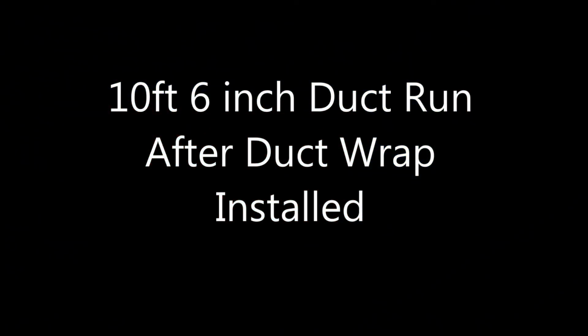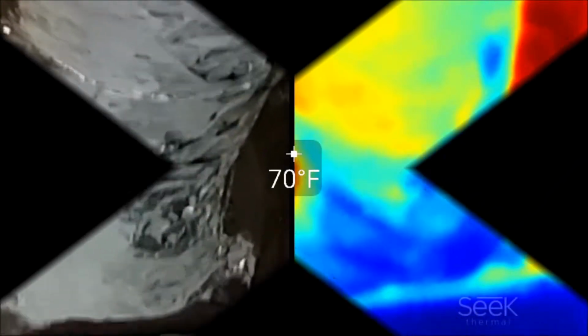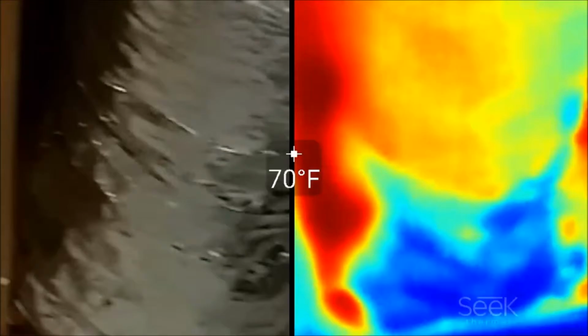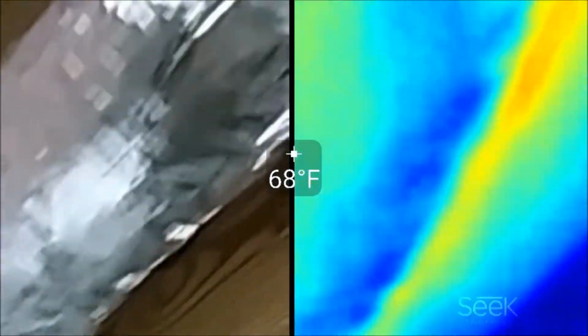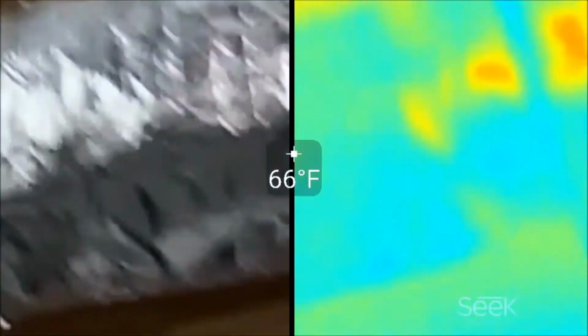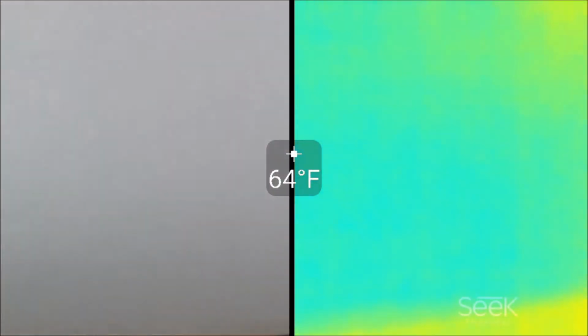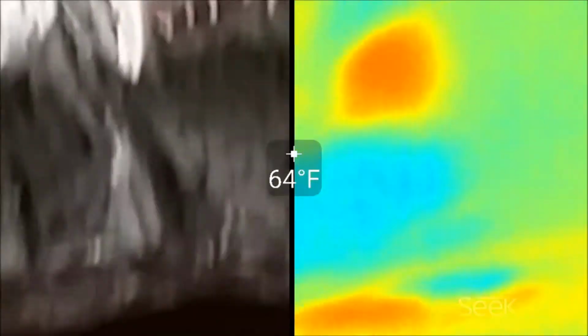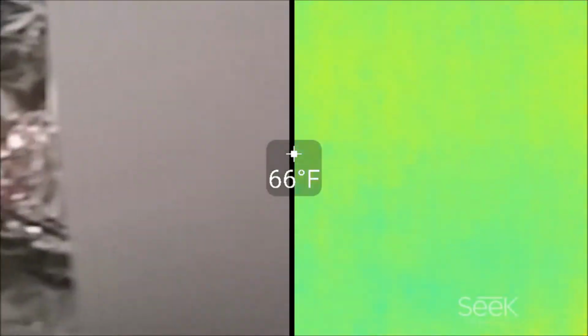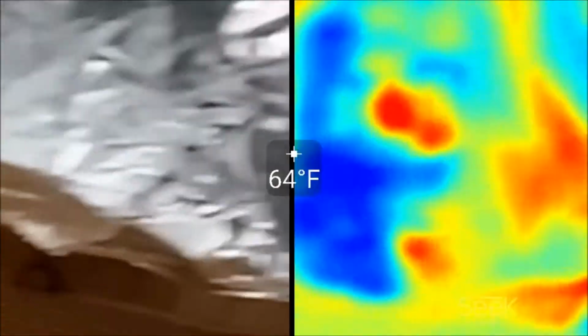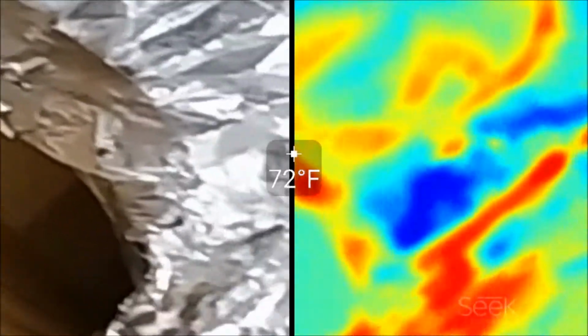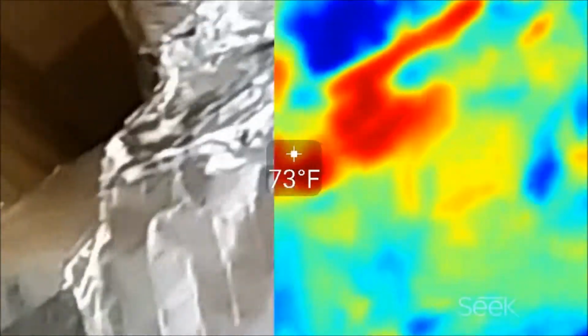So now we're going to go back underneath and look at the ducts with the wrap installed. Again, with the thermal imager, I'm able to look at the duct insulation, which looks like it's dropped significantly. Before it was about 95 degrees that we could read on that pipe, and now it's in the mid-60s. So obviously the duct wrap is working. You can see here there's some hot spots. It's not perfect, but it's definitely a significant drop.